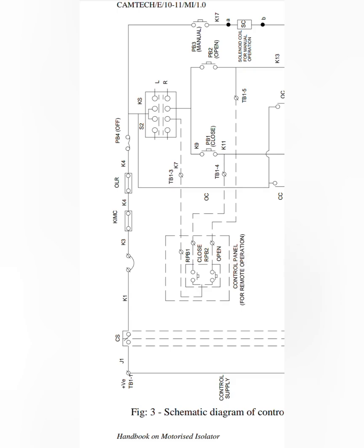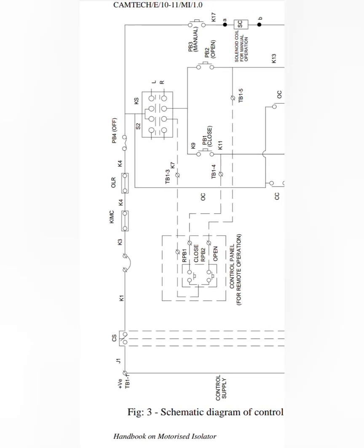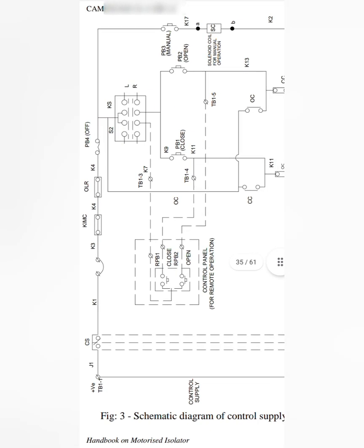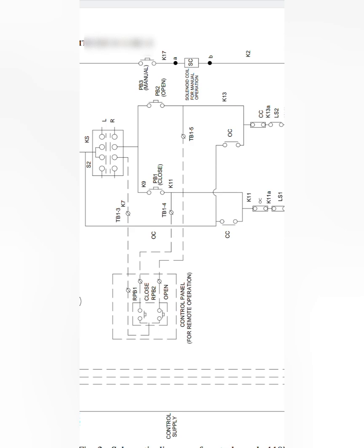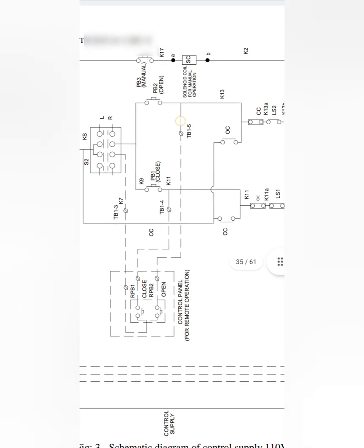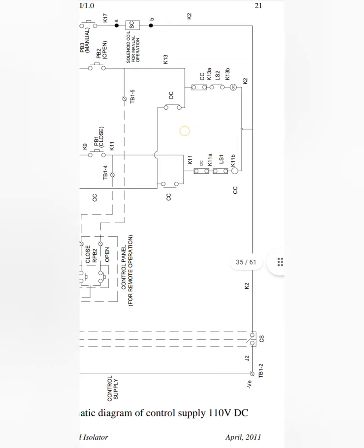Coming up to PB4, which is your push button 4 — this is for your manual operation. Then coming to KS and LR, which is your local and remote switch. If the isolator needs to be operated locally in that yard itself, we will use the local switch, turning it into local mode. If the isolator needs to be operated remotely, which means through a SCADA operation, we need to select remote mode.